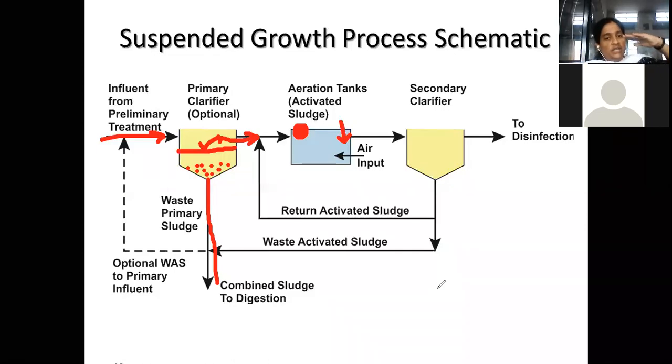So when it is rotating at 1000 RPM, at that time atmospheric oxygen will mix into the water. Atmospheric air will mix into the wastewater, and while mixing, it will dissolve the oxygen into the wastewater, and at the same time whatever odorable gases are present in that particular tank will start emitting. Meanwhile, the dissolved oxygen level of this tank is going to increase, and odorable gases from the wastewater start emitting out.